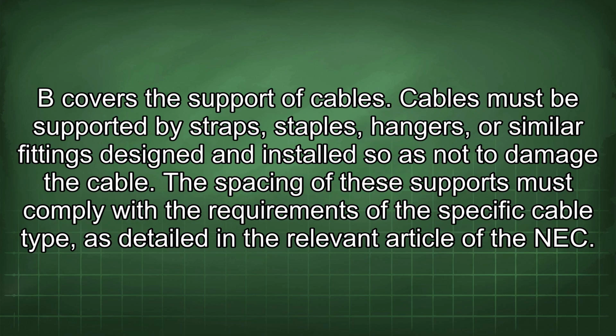Cables must be supported by straps, staples, hangers, or similar fittings designed and installed so as not to damage the cable. The spacing of these supports must comply with the requirements of the specific cable type, as detailed in the relevant article of the NEC.